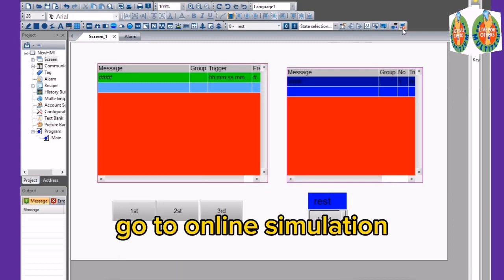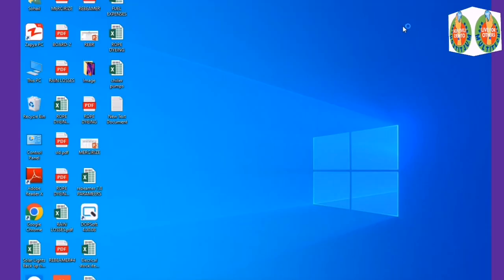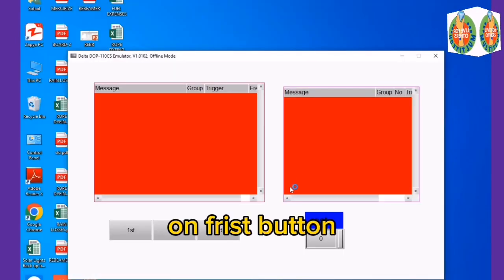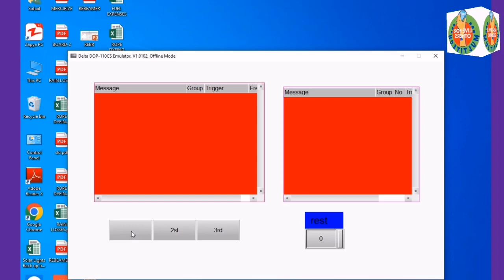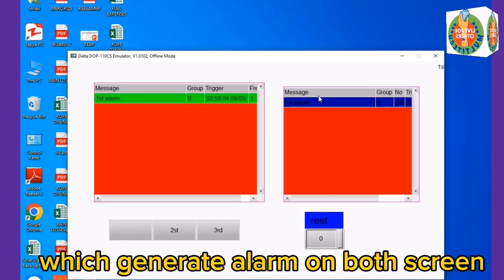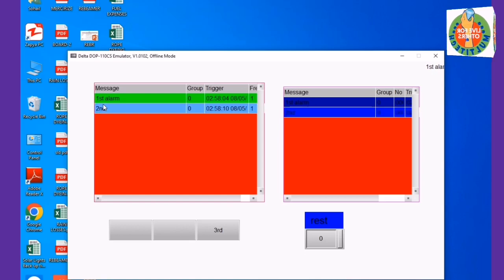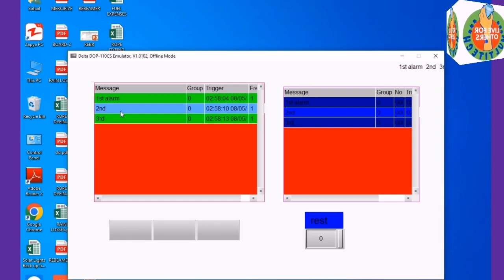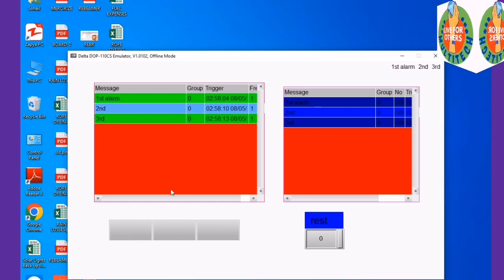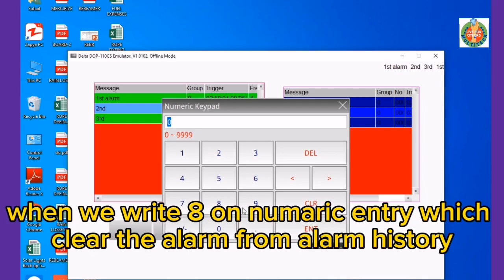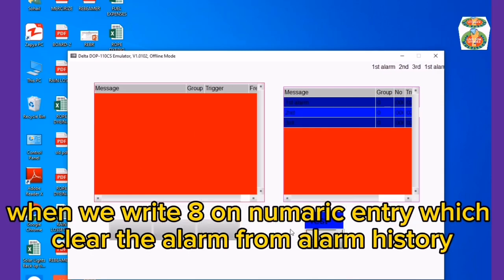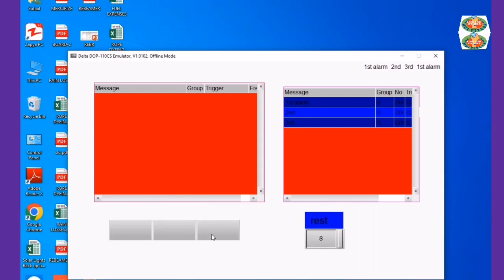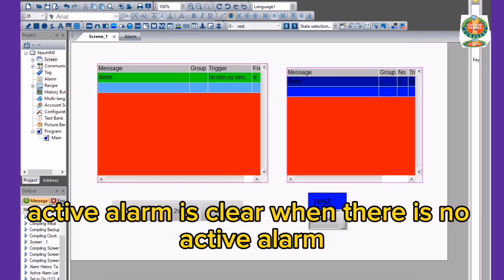Go to Online Simulation. Press the first button, which generates an alarm on both screens. When we write 8 on the numeric entry, it clears the alarm from alarm history. Active alarm is cleared when there is no active alarm.